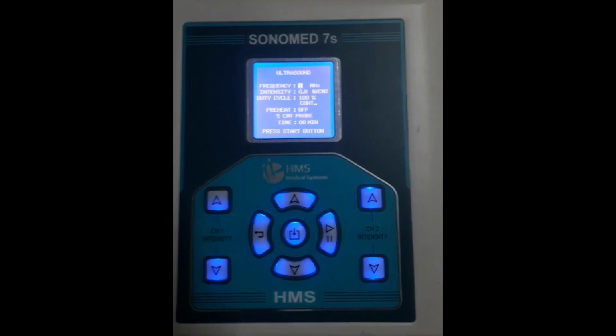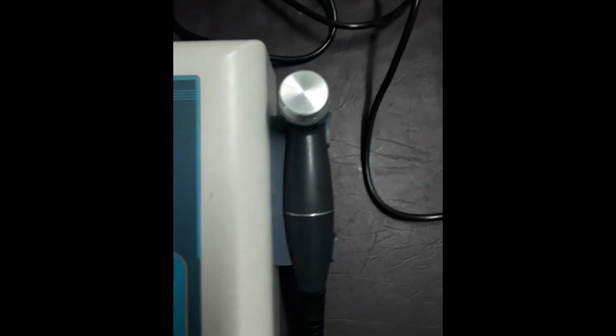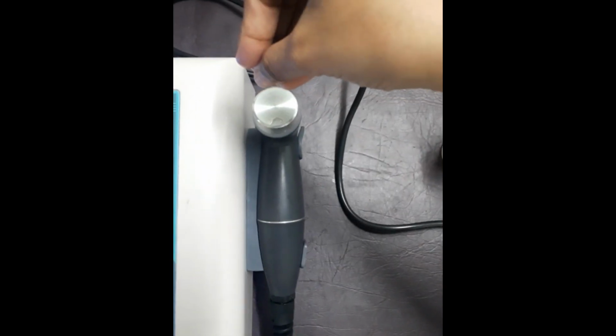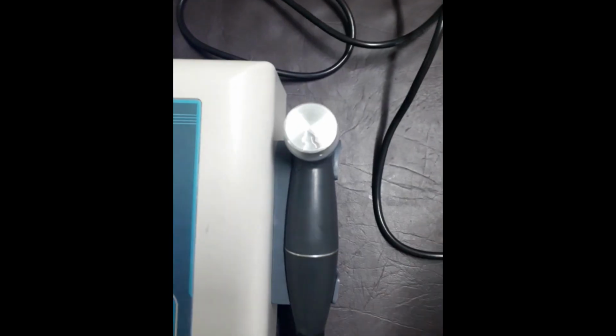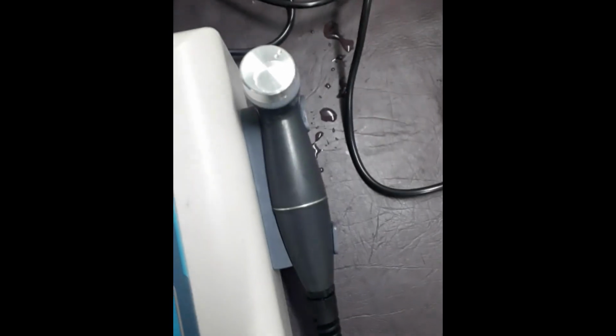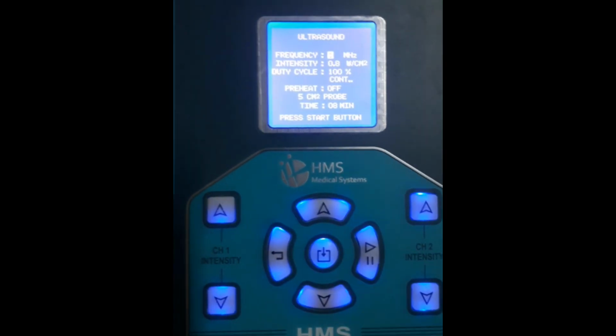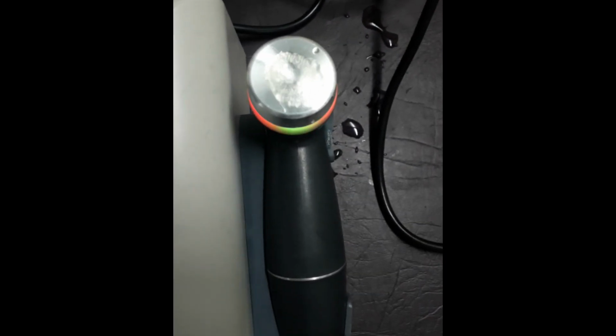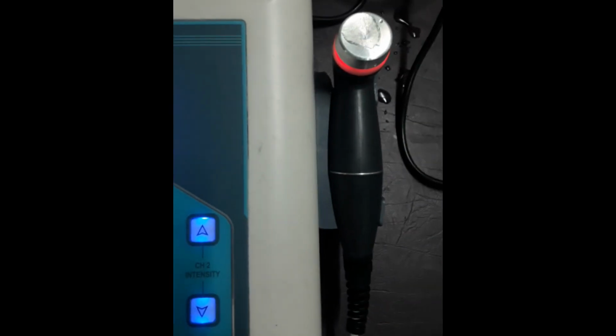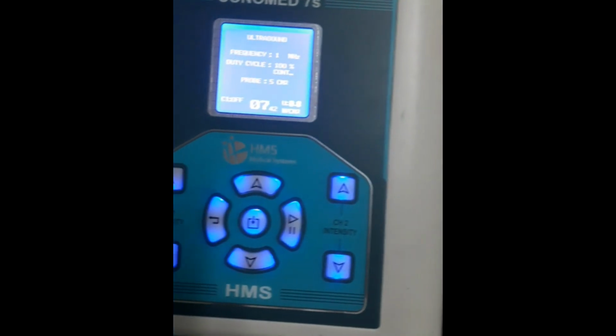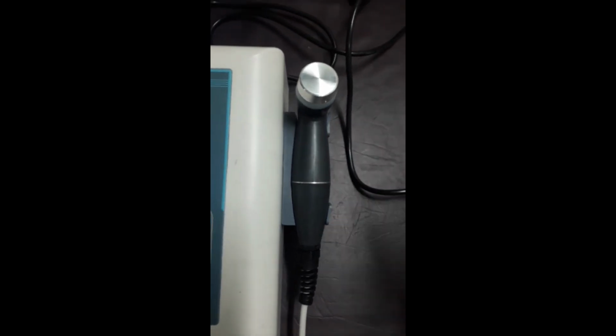Press the start button. In order to check if the ultrasound probe head, that is the transducer head, is working or not, add a few droplets of water and turn on the machine. If you see a ripple effect, it means that the ultrasound probe head or the transducer head is working. Turn off the machine.